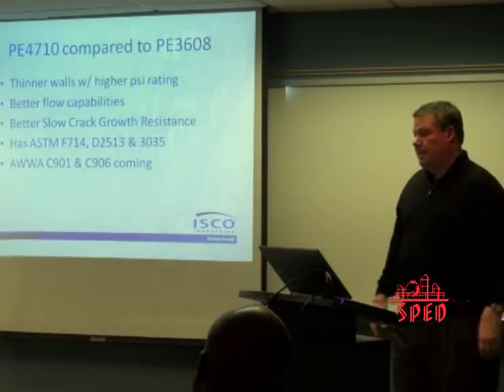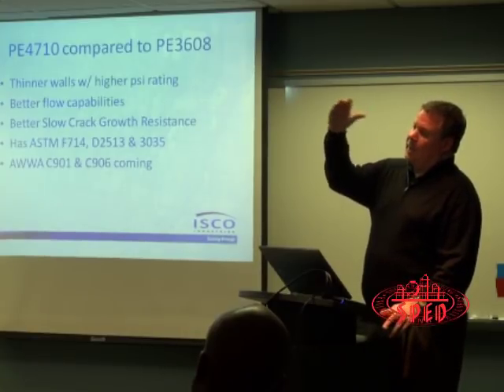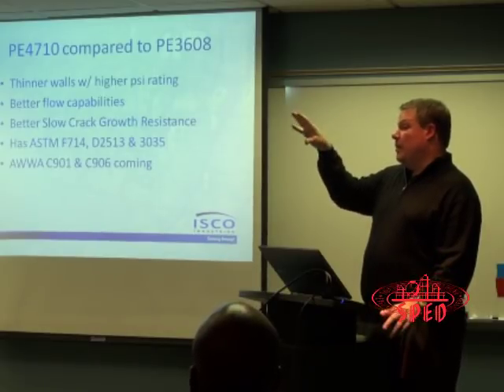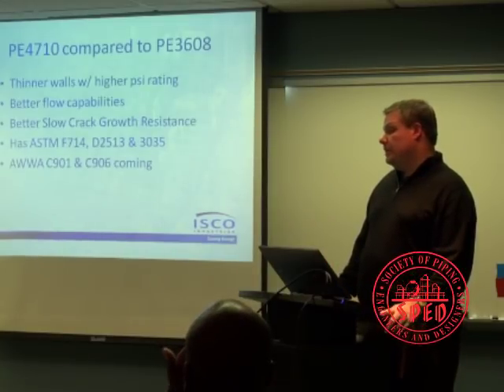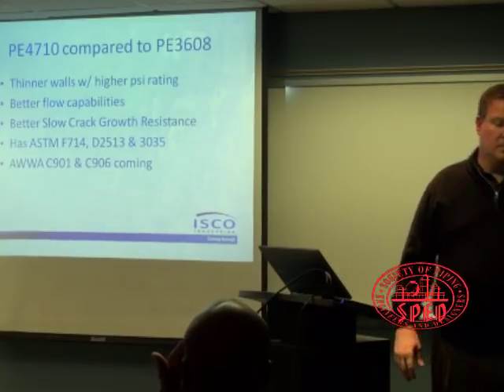OD is the same, so your ID is going to be a little different. Basically, we're dropping up an SDR. So a DR 13.5 now will be rated to 160 PSI, whereas before it would be in the 120 range. Yes, Bill? I was going to comment on the pipe support.